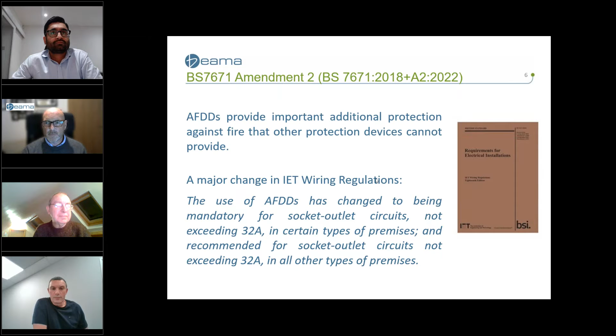Okay, so quickly on to another couple of slides before we get on to the myth element of tonight's webinar. It's just a reminder really, AFDDs do play a really important part in additional protection against fire that other protection devices cannot provide. So a major change in the IET wiring regulations this year was the use of AFDDs has changed to being mandatory for socket outlet circuits not exceeding 32 amps in certain types of premises, and recommended for socket outlet circuits not exceeding 32 amps in all other types of premises. I'm not going to go into depth on that regulation this evening. I think we've seen a lot of webinars and a lot of text on that so far this year. So it's just a reminder slide really.